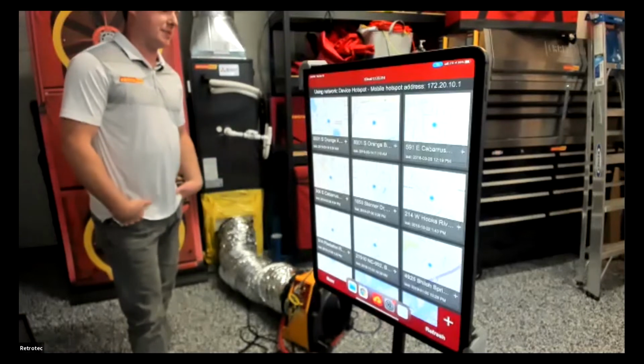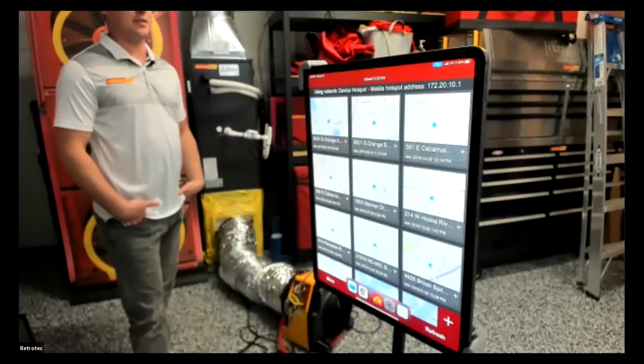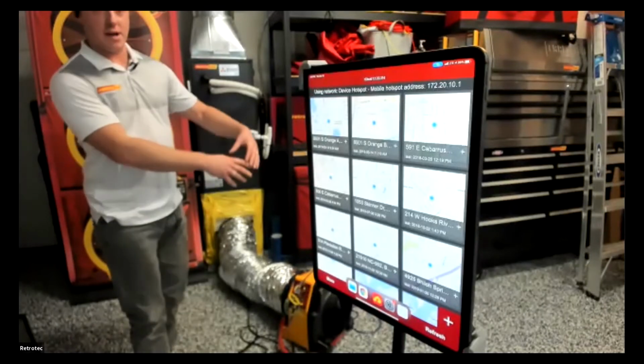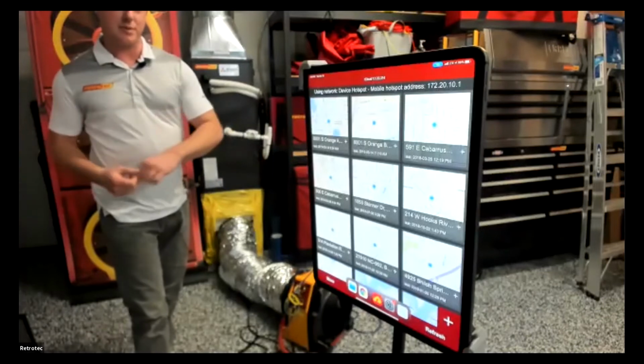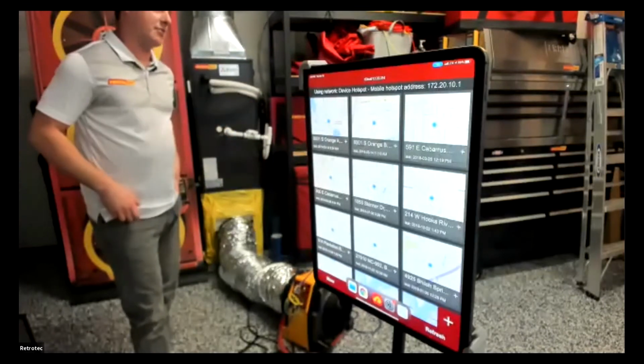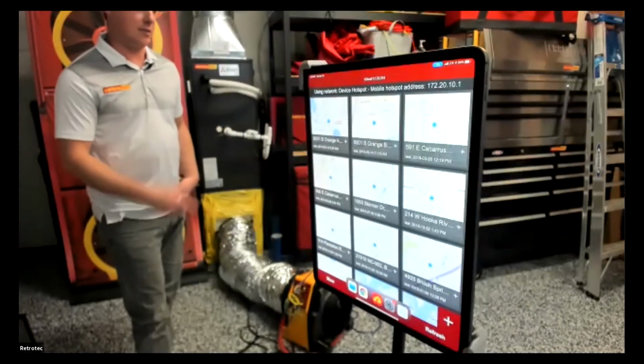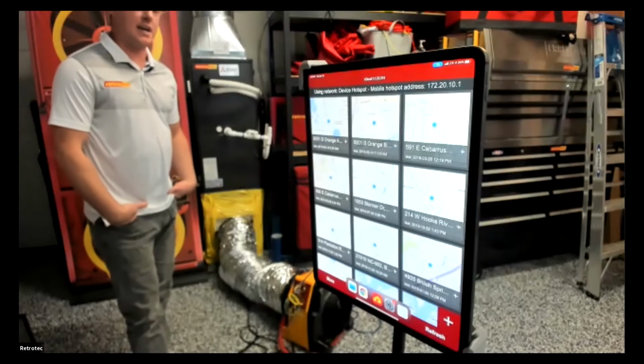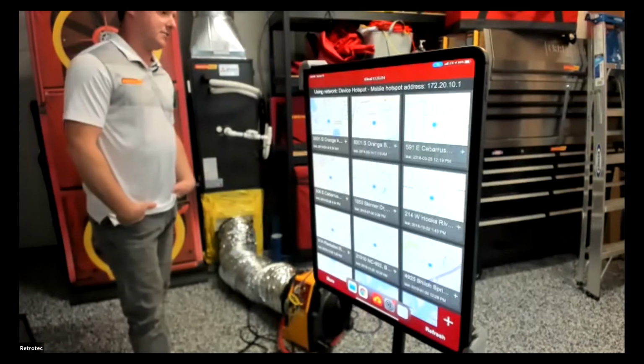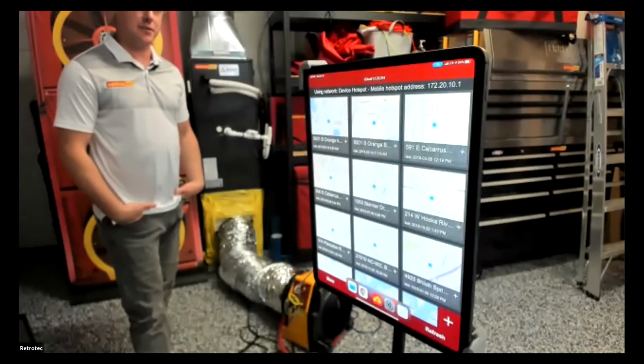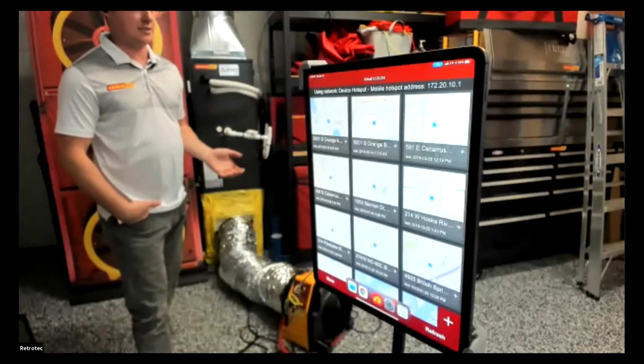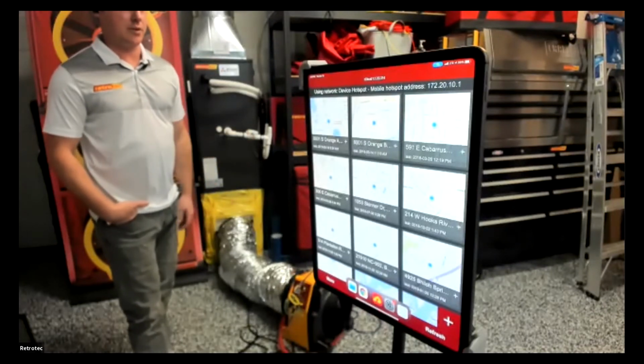And sometimes that can take a lot of tubing you may not have in your bag. So for example, if the duct tester is far away from the blower door in the house, you're going to need more tubing to make that connection happen. That's why most people just go ahead and do the seek to zero. But you can do it that way. We're not going to demo that today, just for time. We're just going to show how to do a duct leakage to the outside test manually with seeking zero.